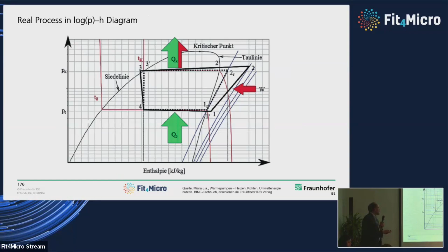The efficiency of a heat pump depends on the temperature levels, and this is really a big difference to the standard way we are heating currently, because condensing boilers do depend a bit on the temperature level at which they deliver heat. If they have to deliver at 70 or at 50, there's a small condensation effect. This is why they're called condensing boilers, but that's a few percent. For a heat pump, this makes a huge difference, and for a heat pump, there's a second temperature which is just not there for the condensing boiler, which is the source temperature, and this is mainly ambient.